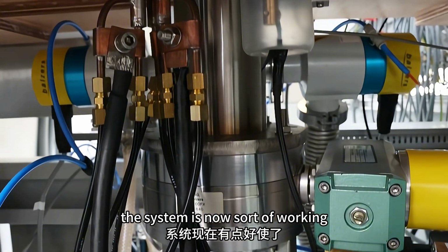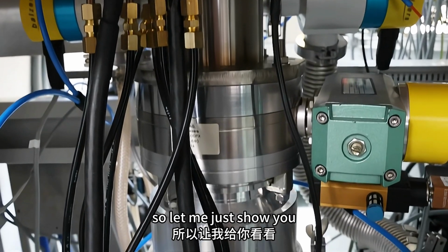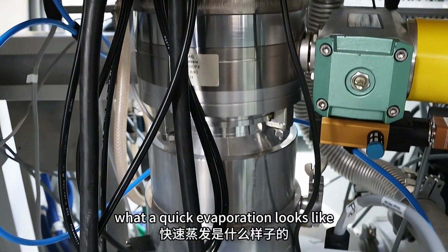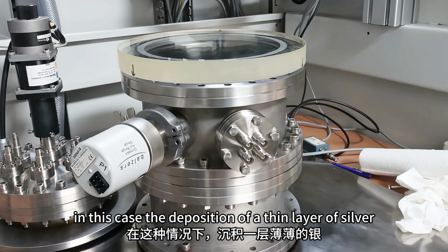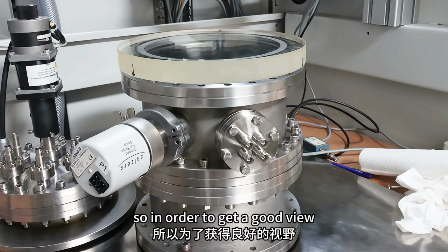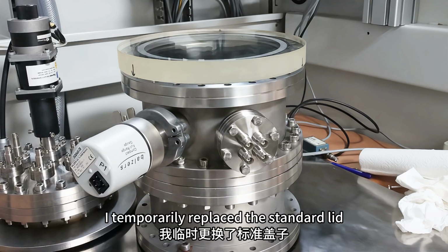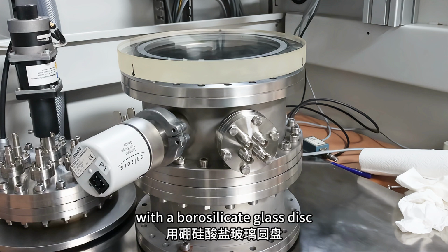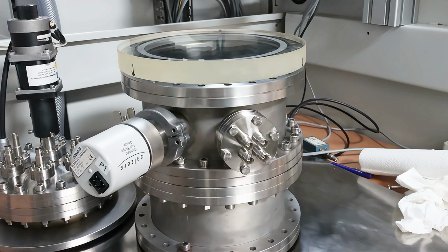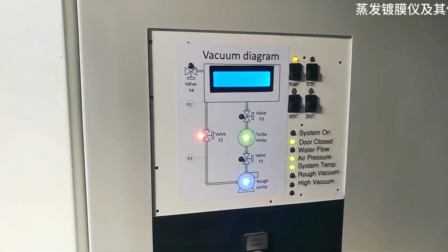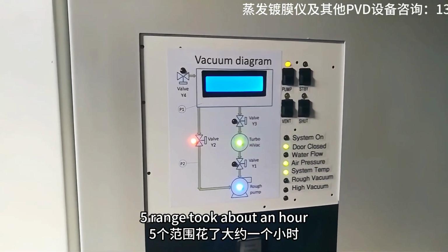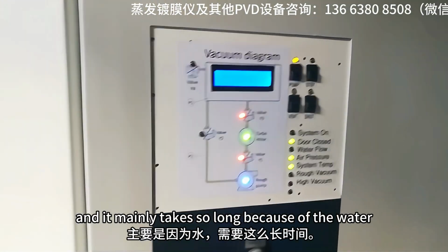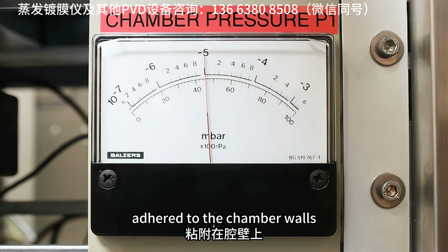The system is now sort of working, so let me just show you what a quick evaporation looks like. In this case, the deposition of a thin layer of silver. So in order to get a good view, I temporarily replaced the standard lid with a borosilicate glass disc. Pumping down to the 10E-5 range took about an hour, and it mainly takes so long because of the water adhered to the chamber walls.